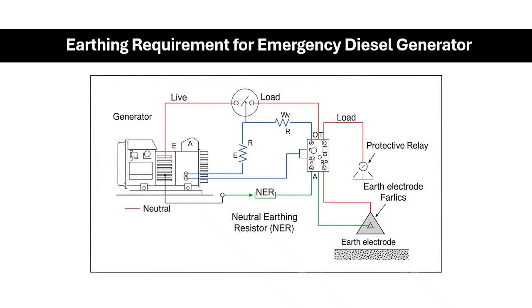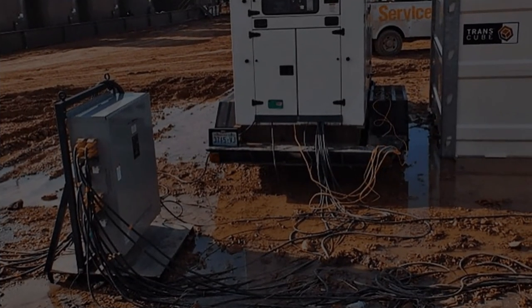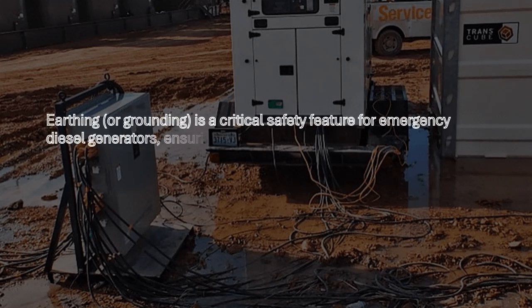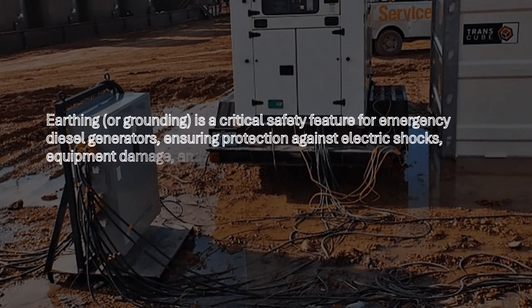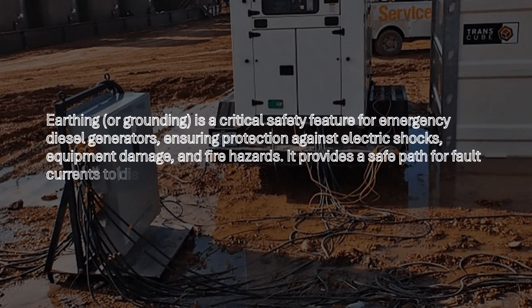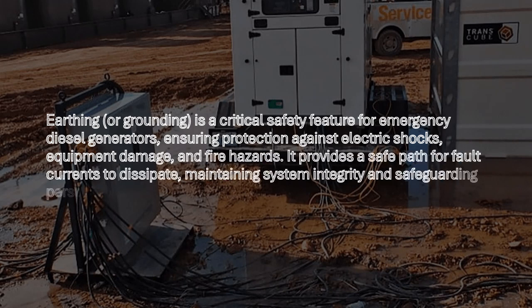Earthing requirement for emergency diesel generator. Enhanced guide. Earthing, or grounding, is a critical safety feature for emergency diesel generators, ensuring protection against electric shocks, equipment damage, and fire hazards. It provides a safe path for fault currents to dissipate, maintaining system integrity and safeguarding personnel.